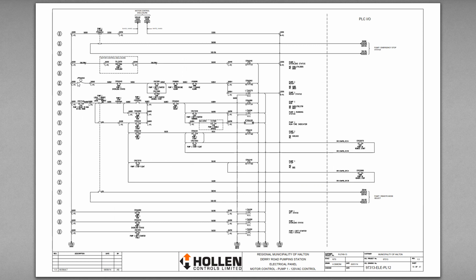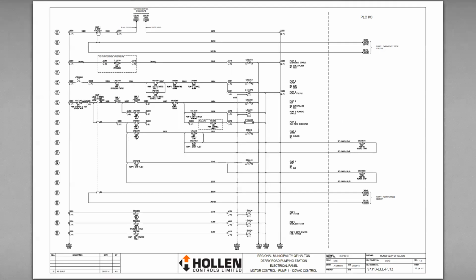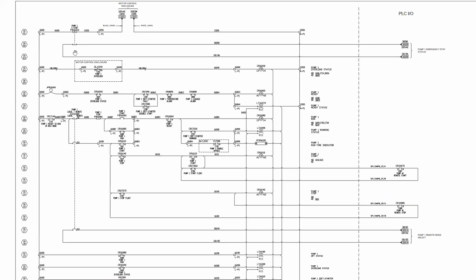So you're showing here, this is actually a jumper. It's a loop of wire that you could actually see. You've got e-stops up here. When the e-stop's pressed, you have a status for it, but it actually opens up power to prevent things from happening. So the e-stops have to be pulled out.